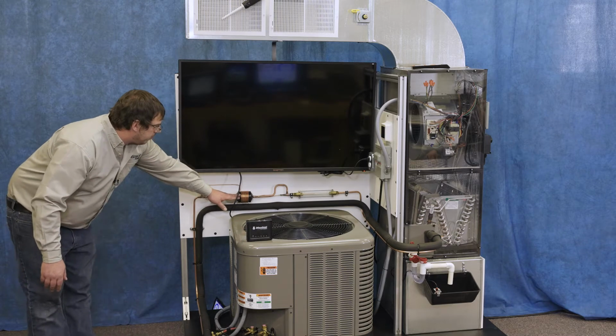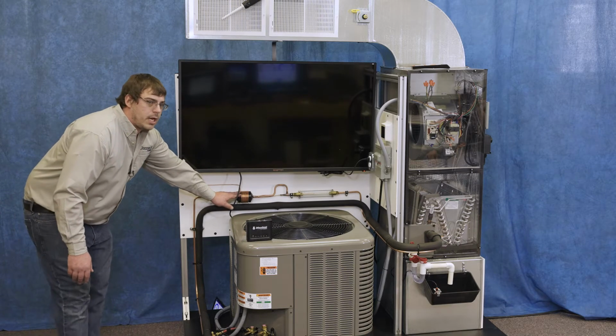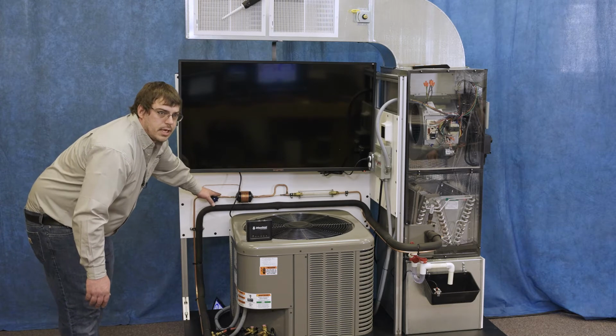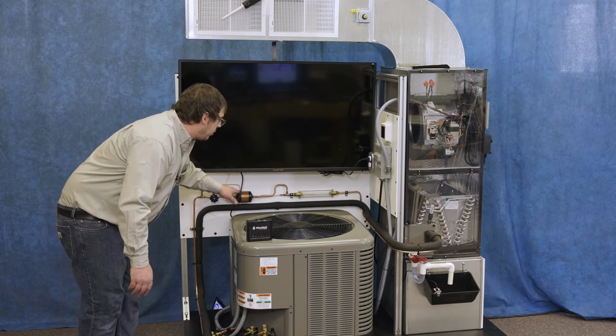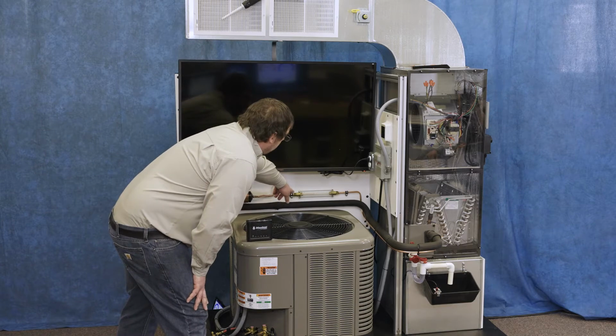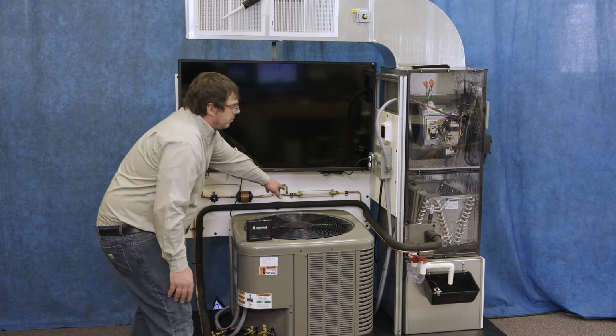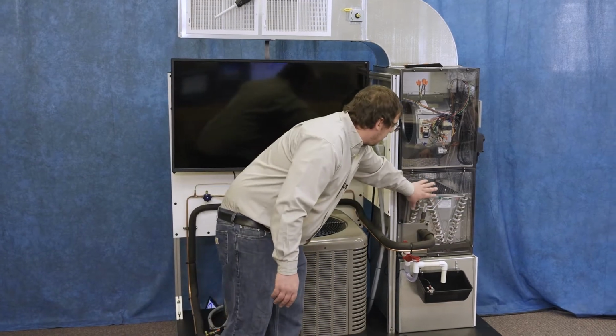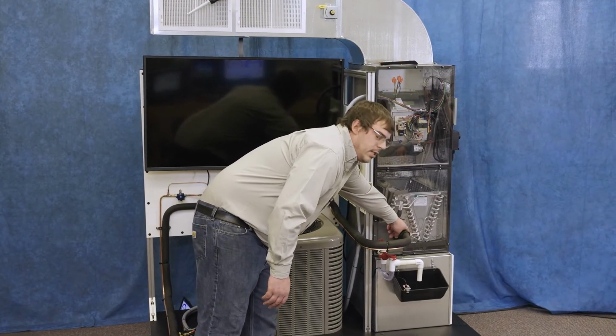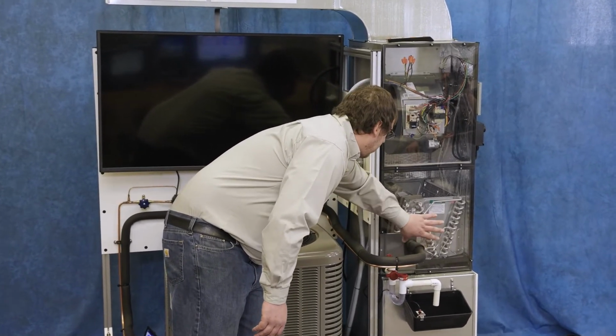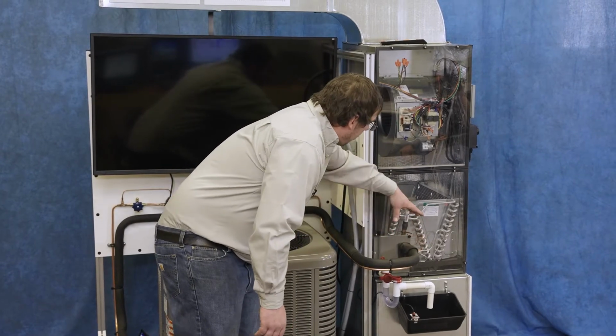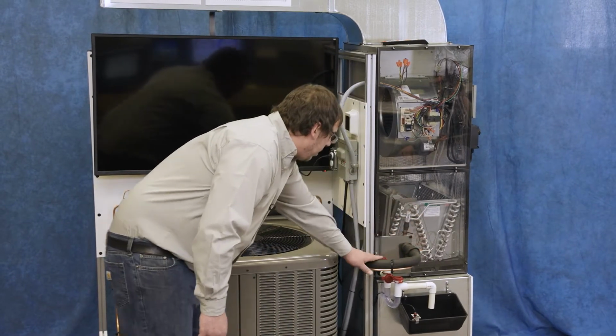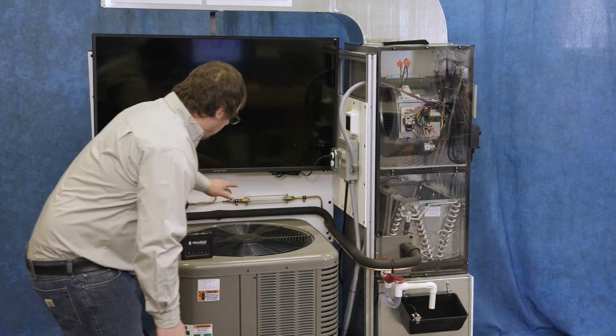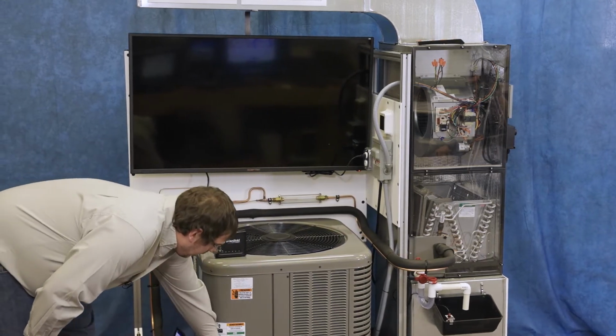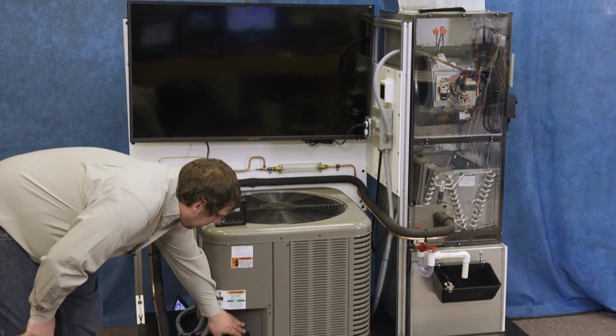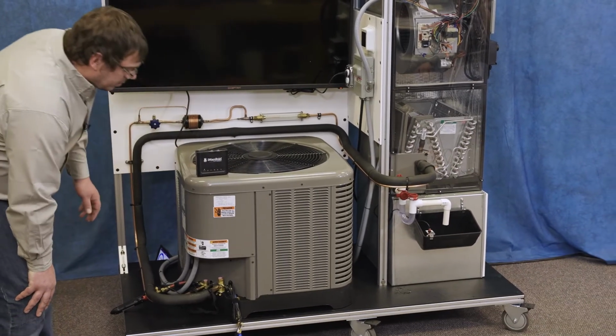This is where we've got another fault right before the filter dryer, where we can simulate a restriction there, forcing the refrigerant through the capillary tube. We've got a sight glass to see that liquid refrigerant. Then coming into the air handler, our indoor TXV is right inside the plexiglass cover through our evaporator coil. And then it's going to come back through our insulated suction line. Coming back down, here's our low pressure service port here, and then back into the compressor.